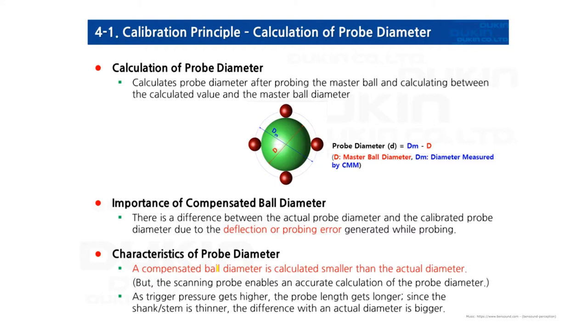You may wonder, why do I have to do this even though I know the diameter of the probe I installed? So the stylus makes contact with the part and delivers the pressure to the module, and inside the module there are pivot points. The pivot points fall apart, then it triggers the signal, and when the signal is triggered it detects the coordinates. So that means the calculated probe diameter would be smaller than the actual size.